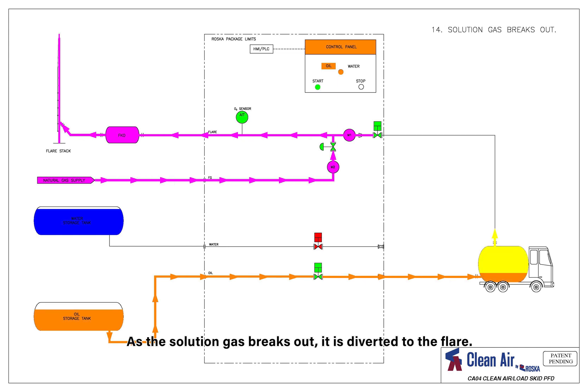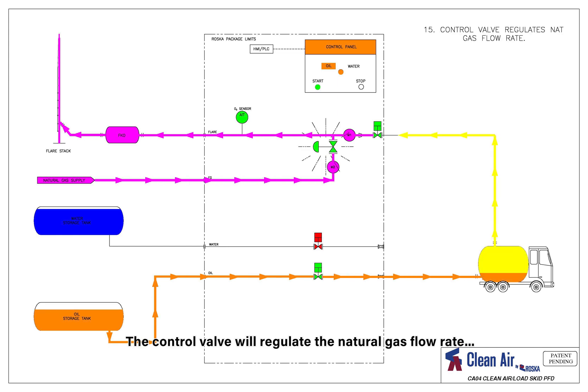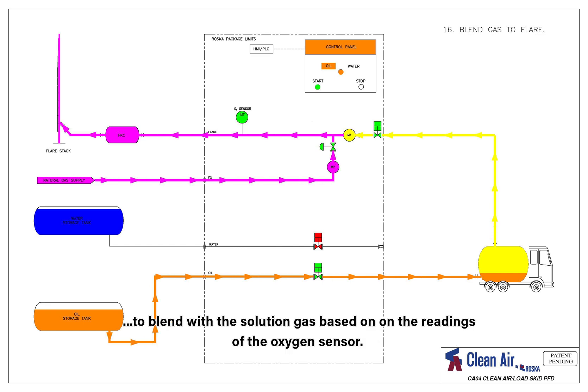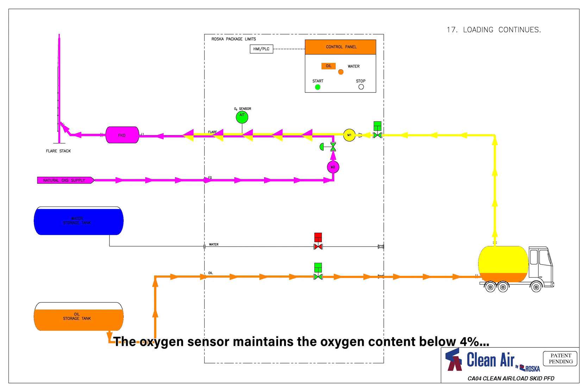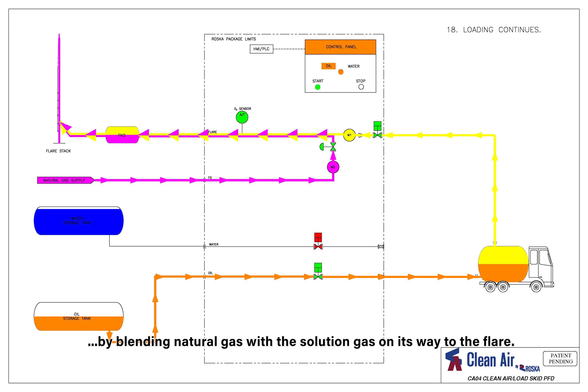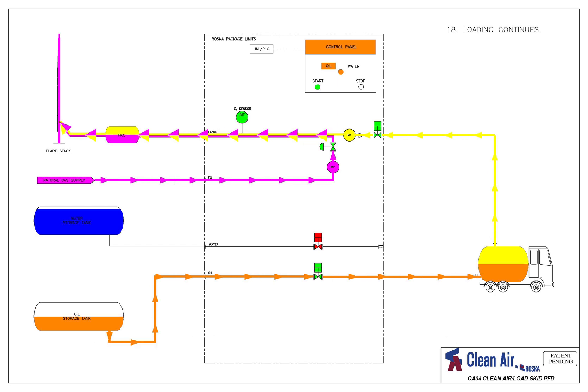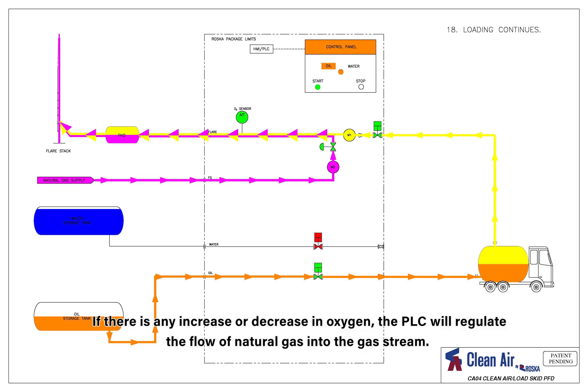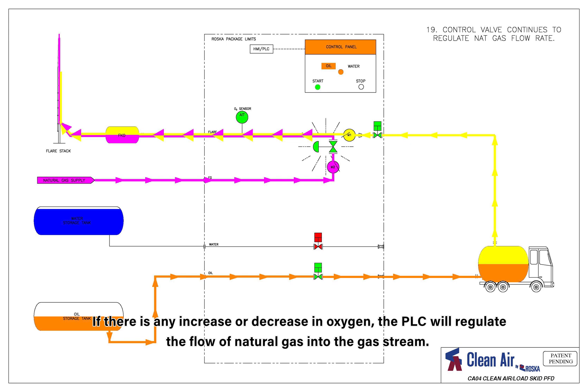As the solution gas breaks out, it is diverted to the flare. The control valve will regulate the natural gas flow rate to blend with the solution gas based on the readings of the oxygen sensor. The oxygen sensor maintains the oxygen content below 4% by blending natural gas with the solution gas on its way to the flare. If there is any increase or decrease in oxygen, the PLC will regulate the flow of natural gas into the gas stream.